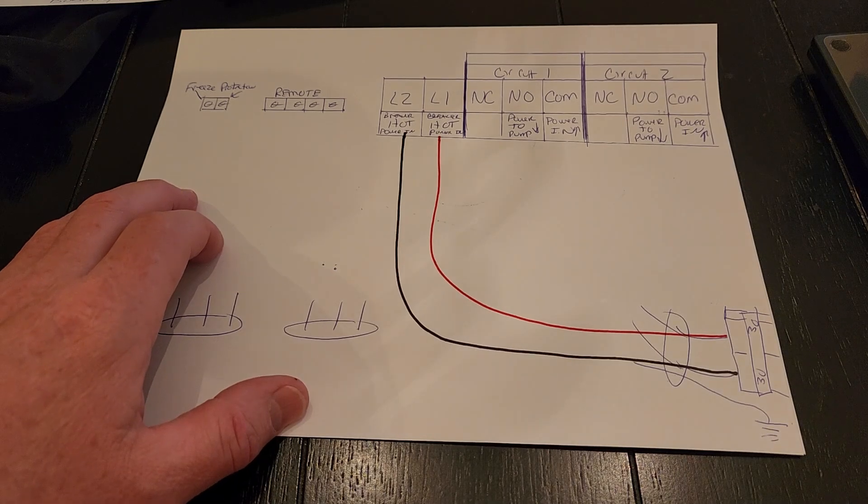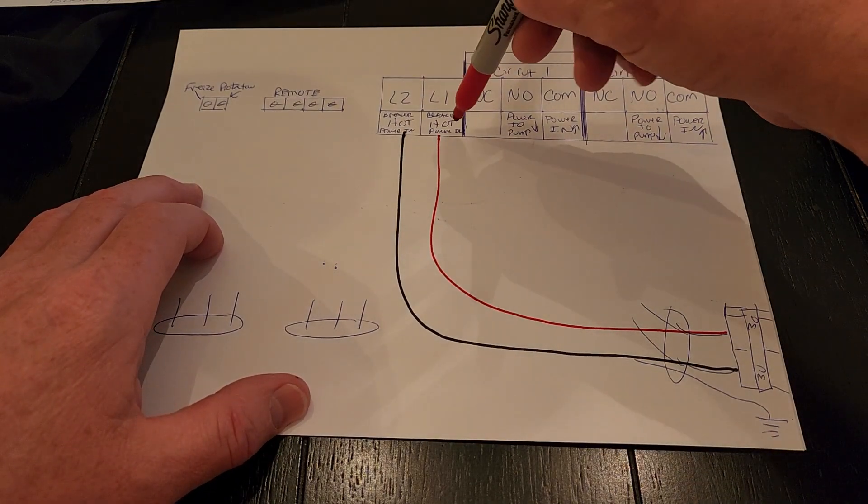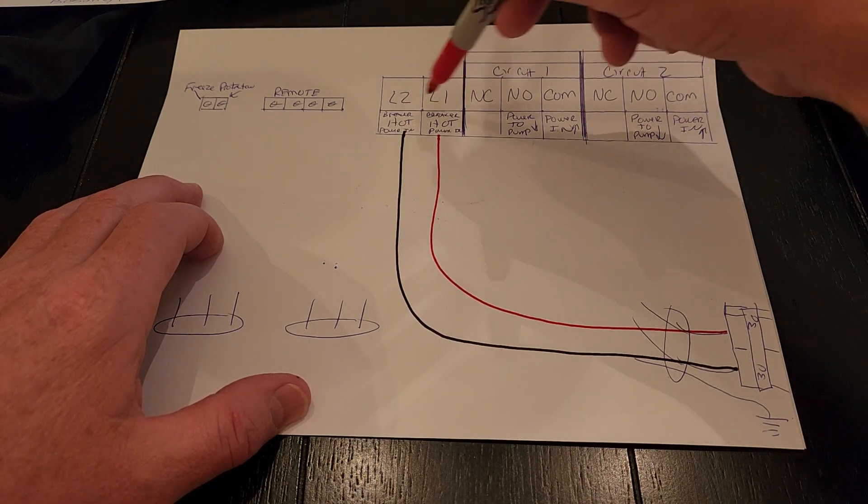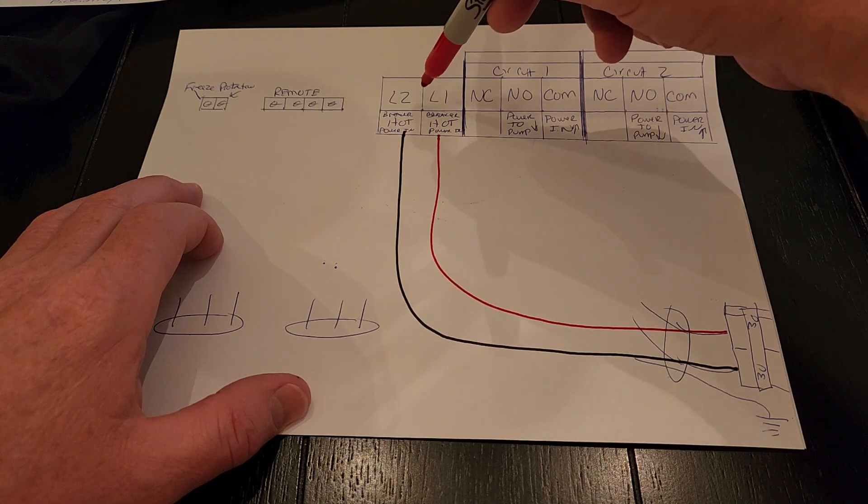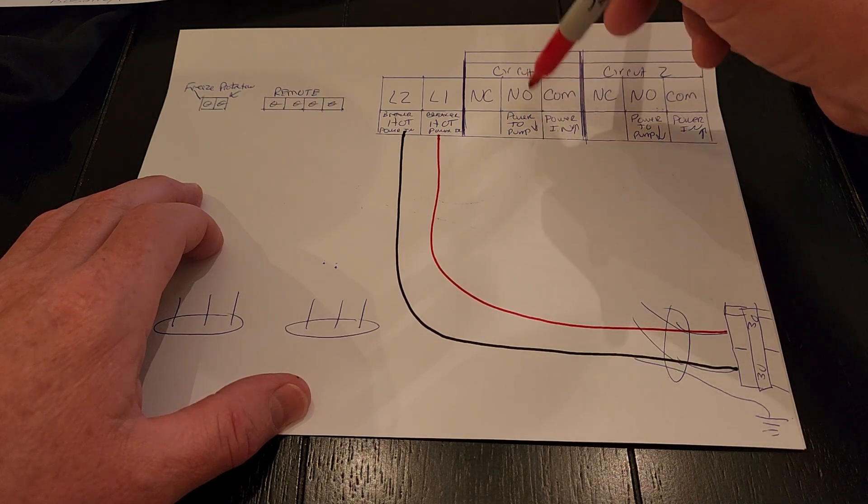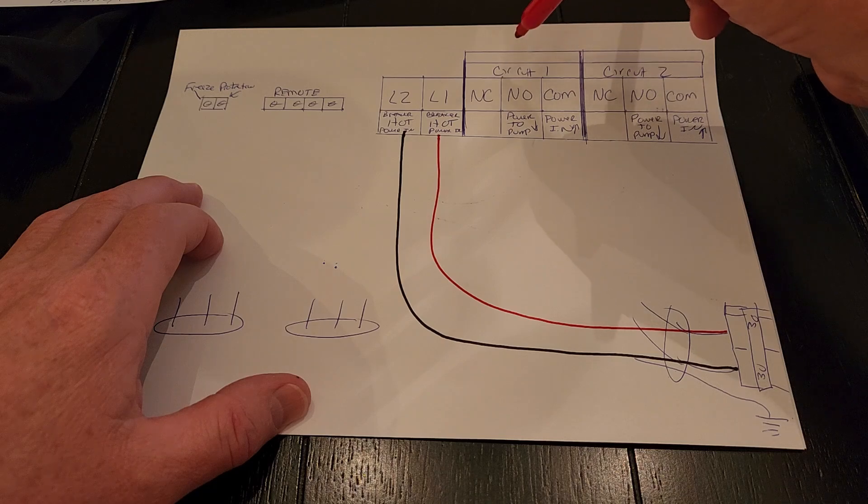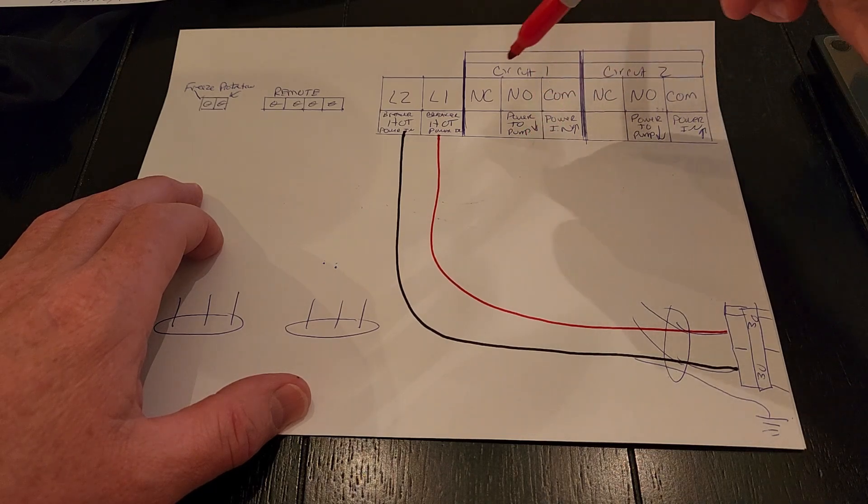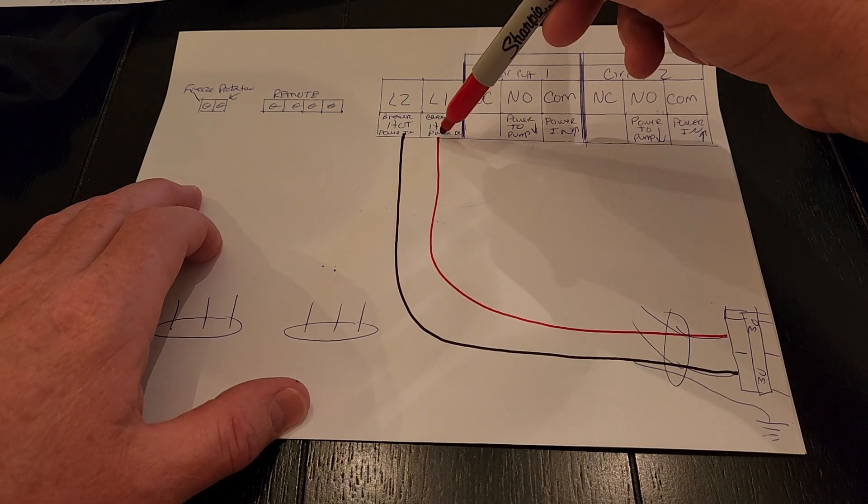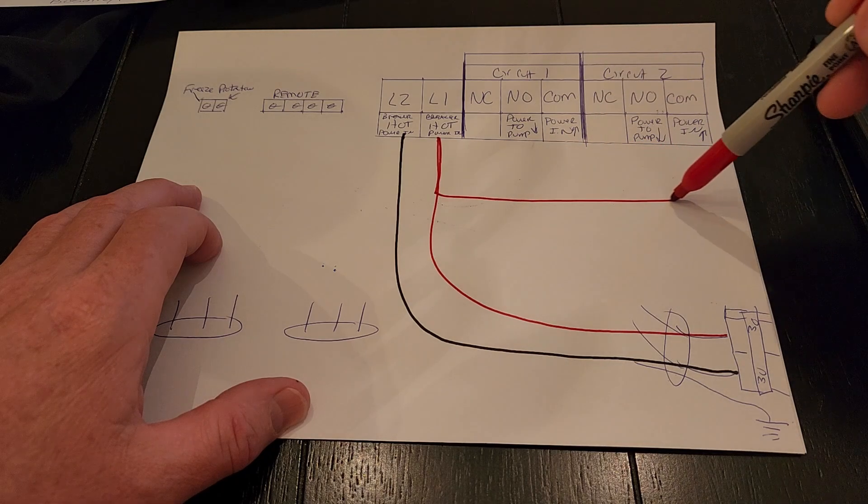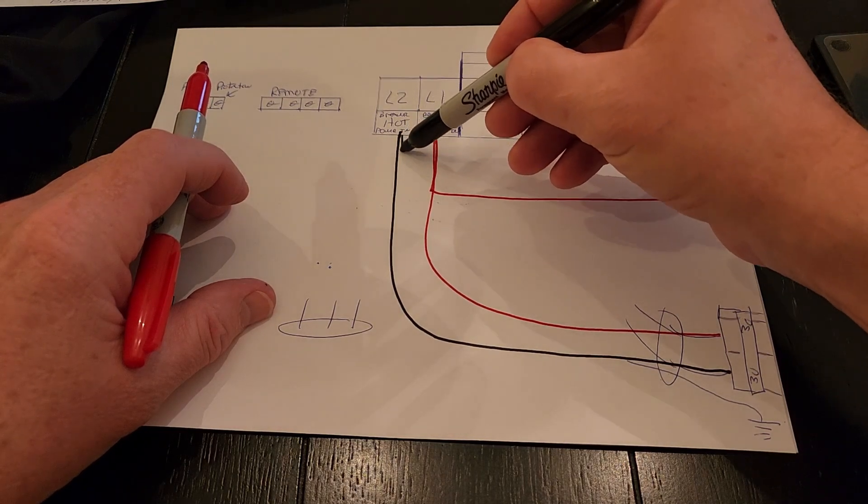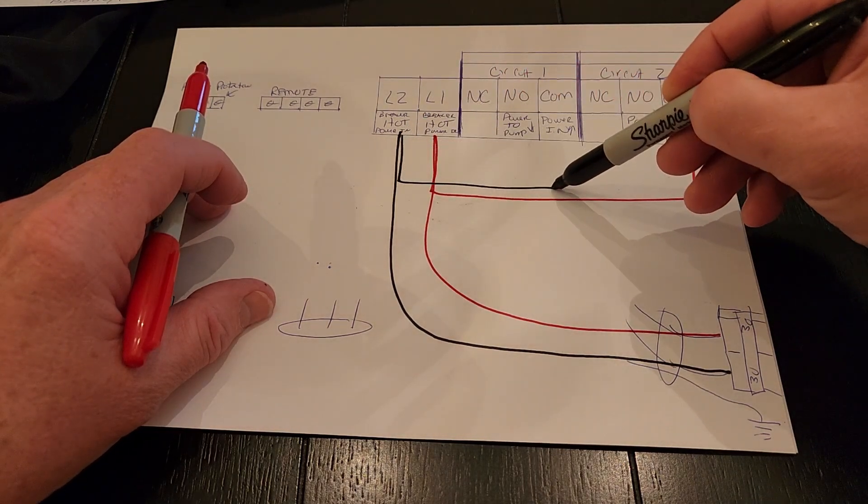For ease of install, we ran the L1 to COM1. This is power in for your pump power. This powers the box. L1 and L2 powers the box. Circuit 1, circuit 2, COM is what power goes in and then comes out the normally open when the power goes in to close the circuit to send power to the pump. So then we jumpered L1 over to COM-IN and then we jumpered L2 to COM1.